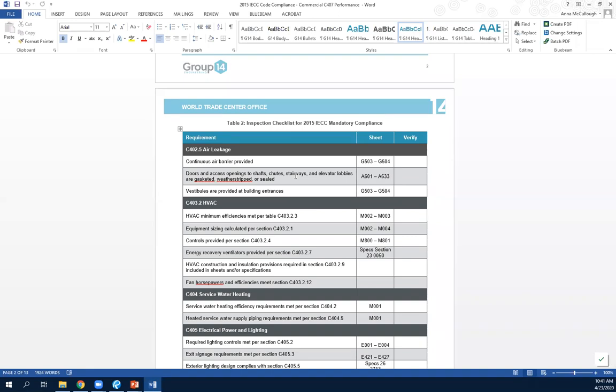So you can, in my opinion, allow more efficient equipment in lieu of an economizer. Now in Denver, it makes a lot of sense. You don't bring in outside air a lot. Yeah, we want to. From about the beginning of May through the beginning of October, it's nice and cool out, and we don't need a whole ton of cooling unless it's August, but still not as bad as you guys.